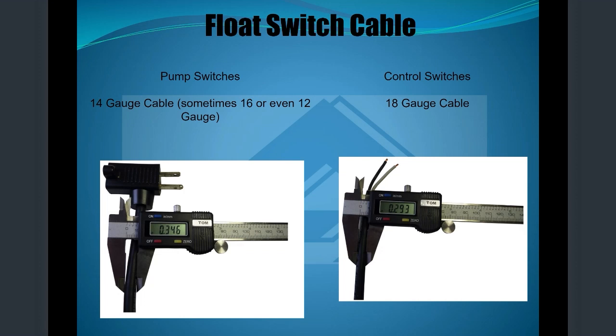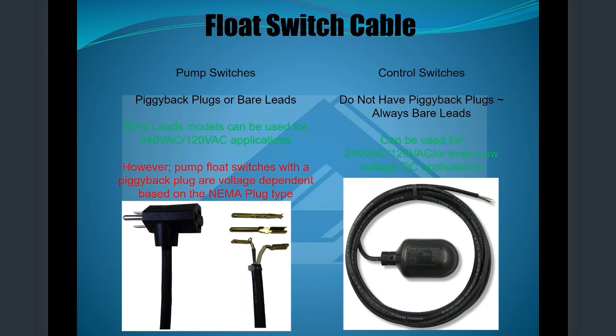All right, next slide. It talks about the different gauges of wire or cable. 14 gauge is common, sometimes 16 or even 12 gauge, and then the control switch is 18 gauge cable. Next up. If you compare the cable on the pump switch and the control switch, you will see they're a little bit thicker or not as thick, depending on what type of cable or how many amps it draws. So this is a 16 gauge wire, and this would be 18 gauge. And like I said, you can get all the way down to 12 gauge for the higher amp cables.